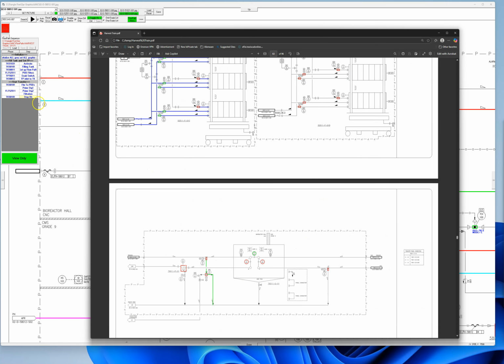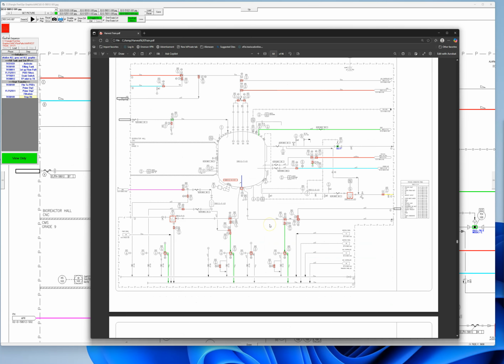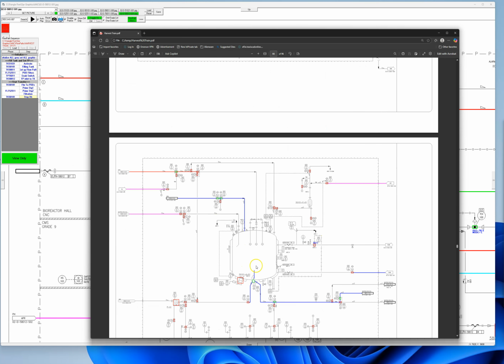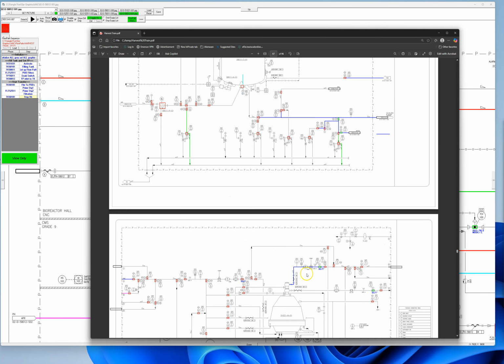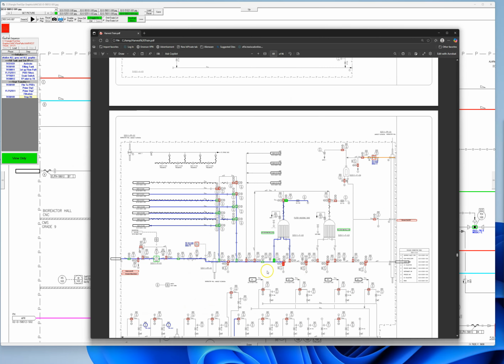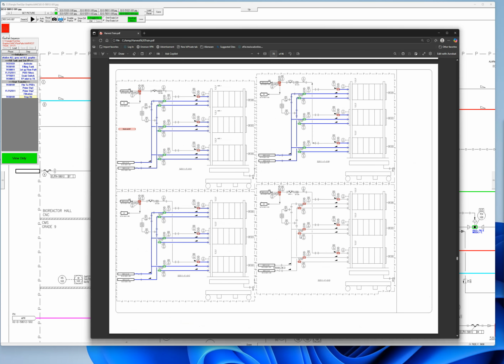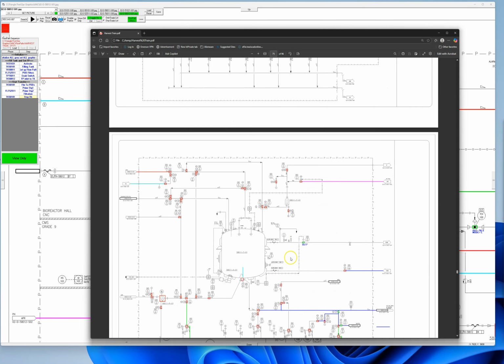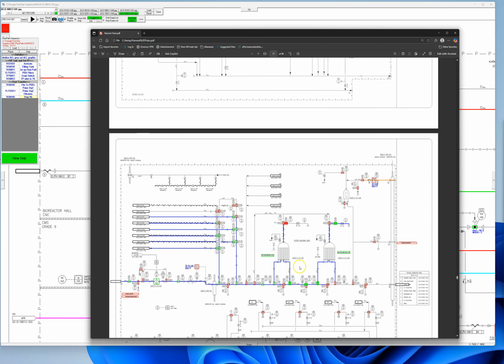And then the next step is we prime stage 1. So again, this is the beginning. We see the flow into the vessel, and this is flowing out from the vessel into the pods. Before it was going to drain, so we close that drain valve, then we open up this valve to do a filtration, priming of stage 1 filter. And then the next step is to do the priming of the next filter, where everything else still stays the same. Again, it shows the differences.